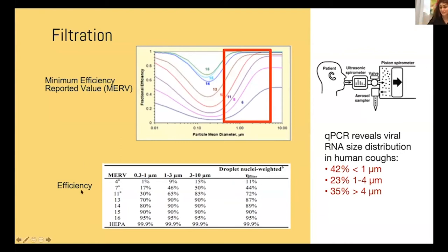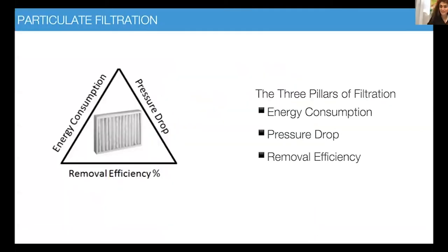Now, if you look at the efficiency table, just to put things into perspective, even if you have a MERV 7 today, you have 44% efficiency. MERV 11, 72% efficient. MERV 13 is 87% efficient. And if you don't know what MERV is, it's a minimum efficiency reported value. It's a rating that gives you, for each filter, a number from 4 to 16. HEPA is not in this same rating. And it gives you an efficiency for different particulate sizes. And the nice thing is that this test is readily available. I'll show you an example later.